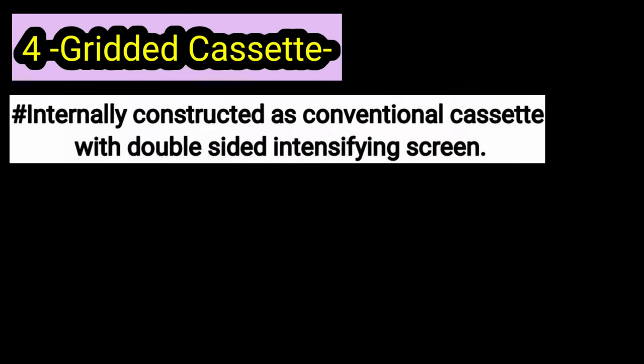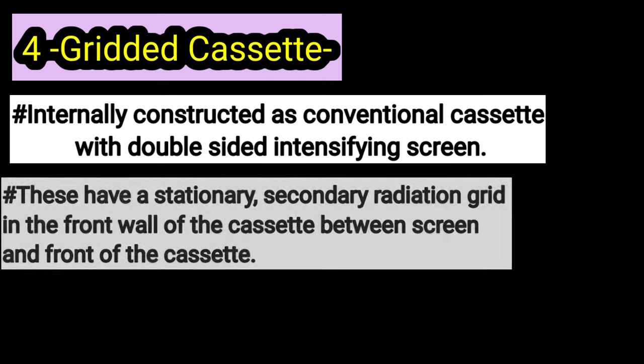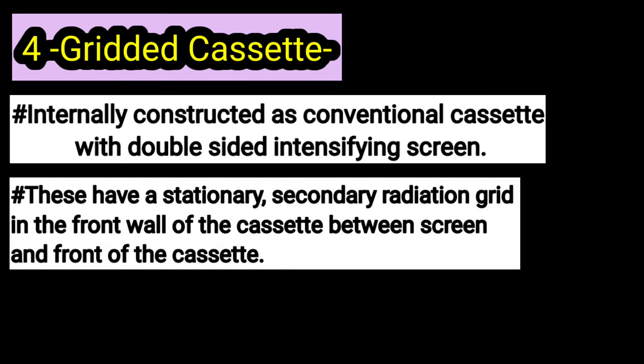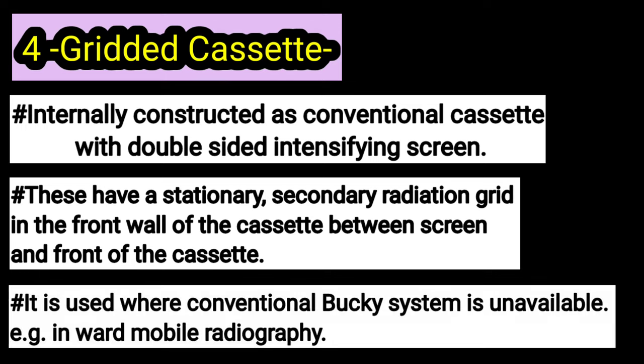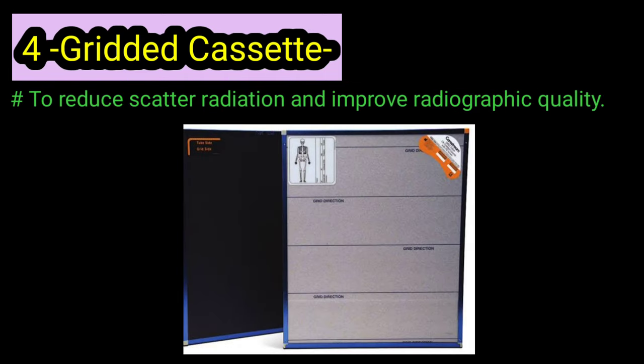The next type is the gridded cassette. The gridded cassette is designed as a double screen X-ray cassette. The only difference is that a stationary grid is mounted on the front side of it. The gridded cassette is used for bedside mobile radiography.